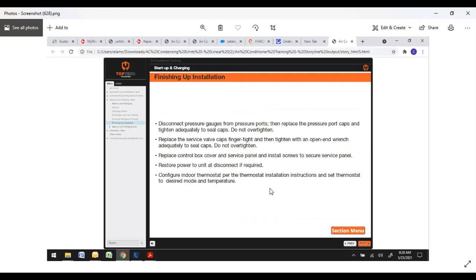So once you finish up your installation, this is huge. Disconnect your pressure gauges from your ports. Check your Schraders, make sure they're not leaking. The big thing is make sure you put your port caps and your Schrader caps on. Don't leave those off, because if you do, people catch that and then they complain. Don't over tighten them.